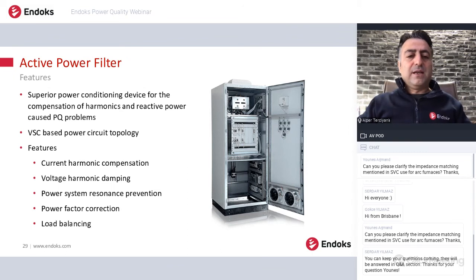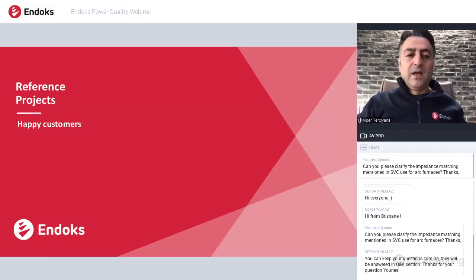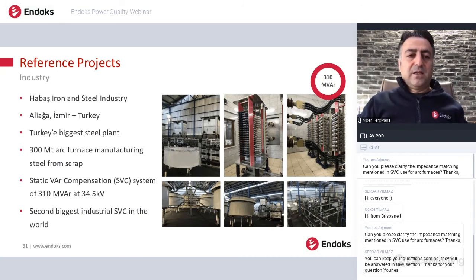Again, the same topology as I told: a voltage source converter based circuit topology. The main features of the active power filters are current harmonic compensation, voltage harmonic damping, power system resonance prevention, power factor correction, and load balancing. And the good thing is, since semiconductor devices are becoming cheaper daily, these active power filters and STATCOMs, especially on the low voltage side, have now become very cost effective devices. We can use active power filters on the low voltage side, maybe rather than using passive filters for eliminating harmonics. And we have some reference projects I would like to explain.